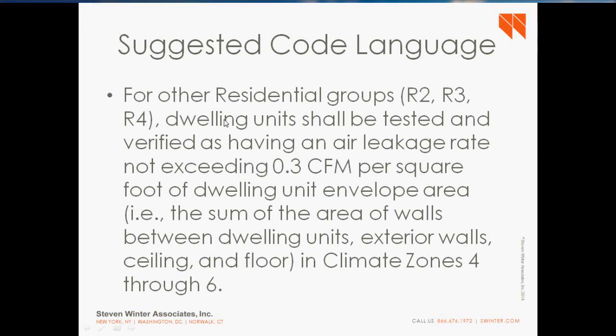So I saw a comment. Someone said it's actually 3 air changes per hour in climate zone 1 and 2. Okay. Yeah, so for New York State, it would be 3 air changes per hour, but we recommend that they go no lower than 5 to start with. 3 air changes per hour is actually a pretty hard out, either of planning on the part of the contractors or adding something like the aerosols to it.